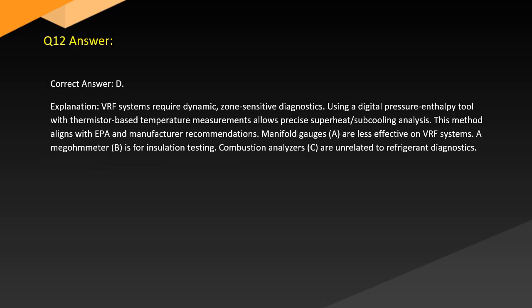Answer. Correct answer: D. Explanation. VRF systems require dynamic, zone-sensitive diagnostics. Using a digital pressure enthalpy tool with thermistor-based temperature measurements allows precise superheat and subcooling analysis. This method aligns with EPA and manufacturer recommendations. Manifold gauges are less effective on VRF systems. A megohmmeter, B, is for insulation testing. Combustion analyzers, C, are unrelated to refrigerant diagnostics.